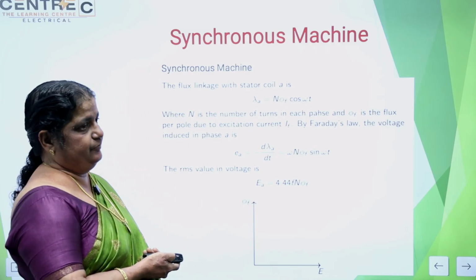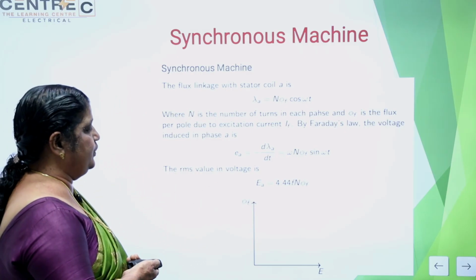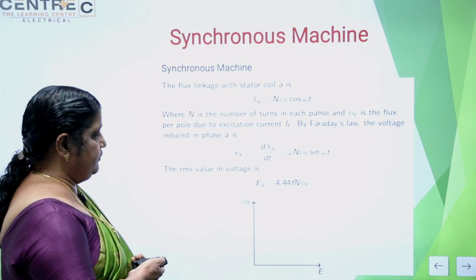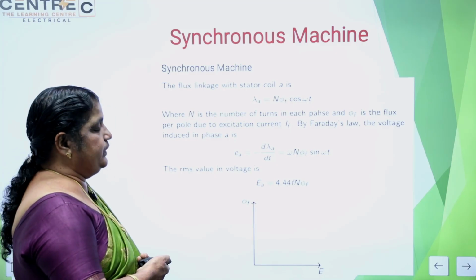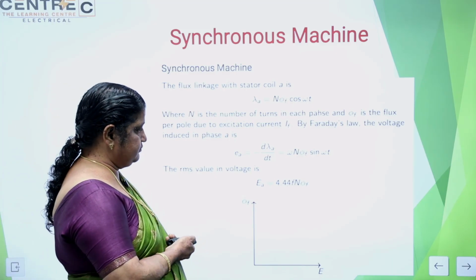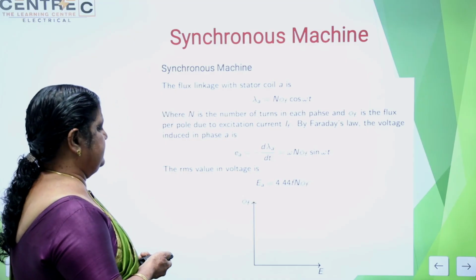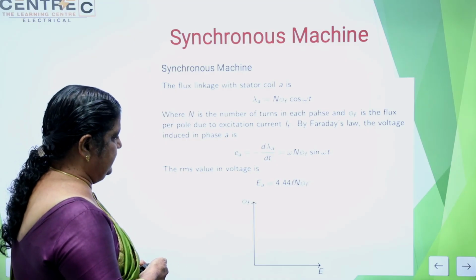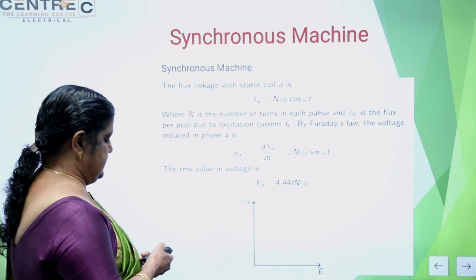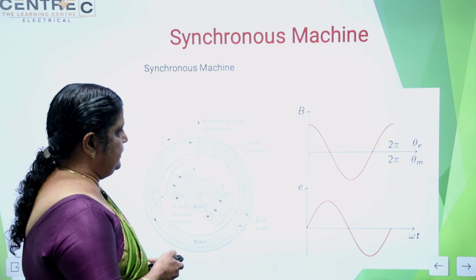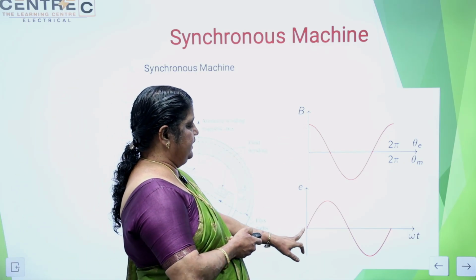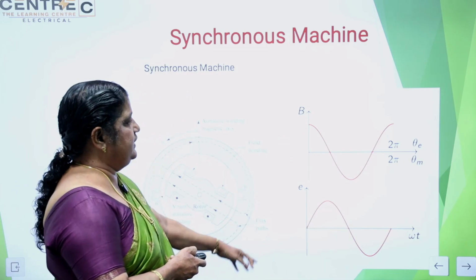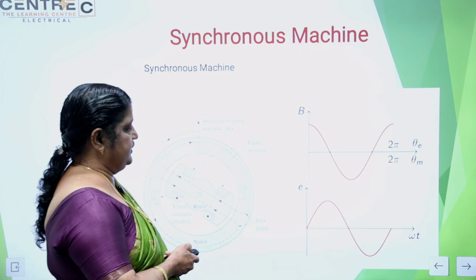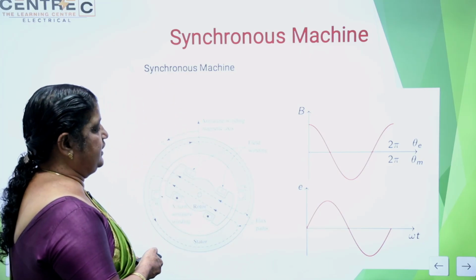The RMS value is 4.44 F into N into phi F, where F is the frequency, N is the number of turns, and phi F is the flux. Then E and phi have a 90-degree phase difference. Here the flux density is maximum, the flux is maximum, but the rate of change of flux is minimum.